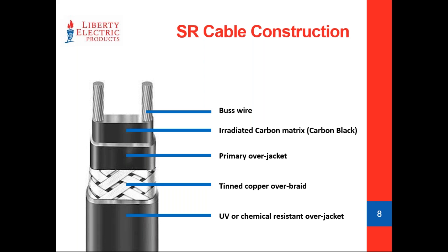The primary over jacket is important to note — it confines the wattage output from going too far down. It doesn't allow the matrix to expand very far. You've also got a tin copper over braid for both protection purposes and as a grounding measure — when you strip the cable back, you can wind up the tin copper over braid and use it as your ground wire. The outer jacket will be either UV resistant, chemical resistant, or both, depending on the manufacturer — suitable for pipe trace or roof and gutter deicing applications.